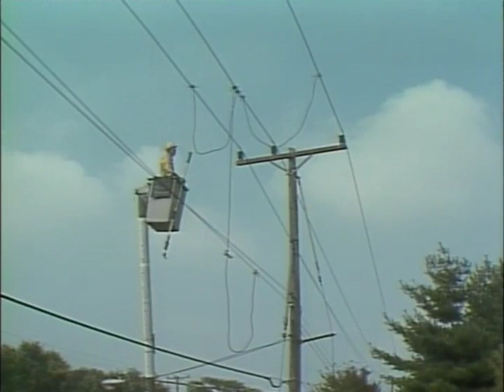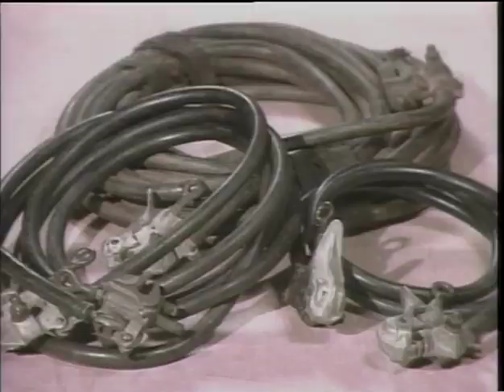Generally, temporary grounds should be located as close as possible to a work area without obstructing the job. They should also be located between the work area and all possible power sources. A grounding set is one type of temporary ground. This one consists of 3 grounding jumpers. Each jumper is a length of insulated cable with a ground clamp attached to each end. The jumpers are clamped between an established ground and the de-energized circuit wires.